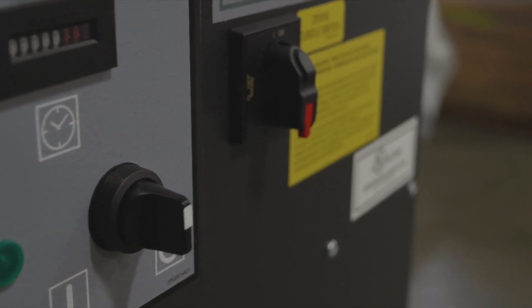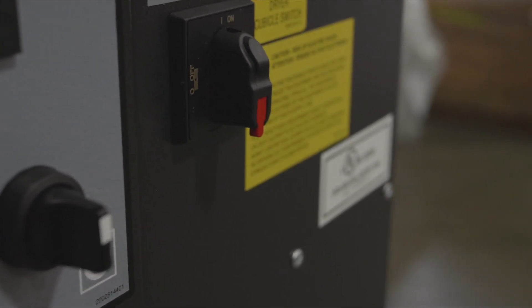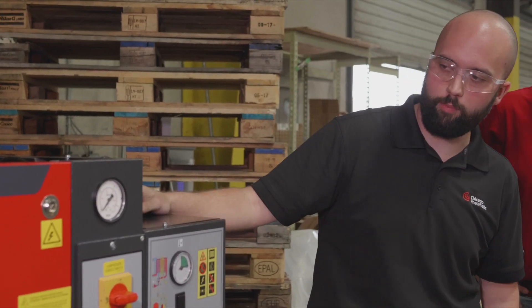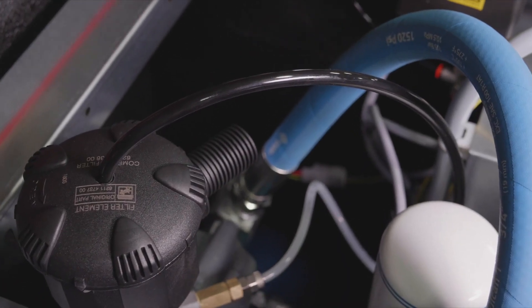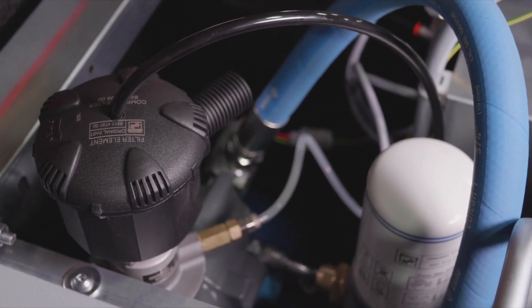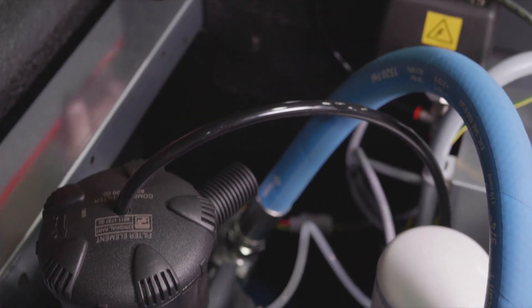Their operation is now running throughout the day, so they need a rotary screw compressor for that continuous performance. It's got the integrated dryer for your air treatment after your air is compressed. It's very easy to maintain, very easy to perform service, and here we just want to give a quick overview of the general orientation of what's inside the cabinet. You've got our oil filters, oil separators, and our air filter here.